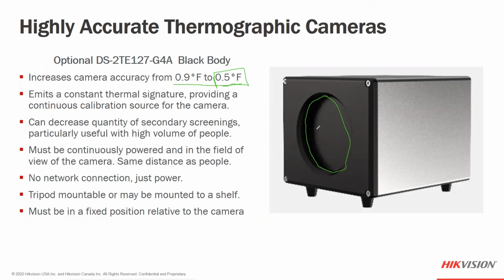This isn't directly connected to the camera in any way, it's visibly in the field of view. You have to be 1, 2, or 3 meters away from the device for the 3, 6, and 13 millimeter cameras respectively. It doesn't have a network connection, it's a physical device that plugs into the wall. You set the temperature on the back, but it has to hang in the field of view, and people can't walk in front of it or block it, or you lose that accuracy level. So it adds some complexity, but creates better overall accuracy.